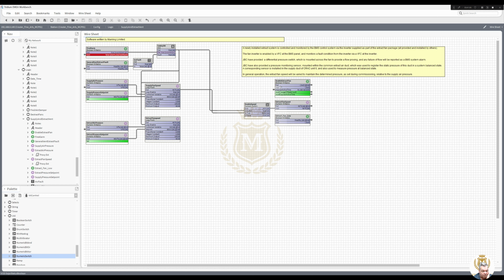We need to enable the fan. So long as the fire alarm and there's no fault, we can run the fan. And the fan will only run faster when the supply air pressure is above 800. Otherwise it will just run at 40%, 20 hertz. But as the supply air pressure increases, that's going to be the wrong way around, isn't it? Yeah, of course it is.